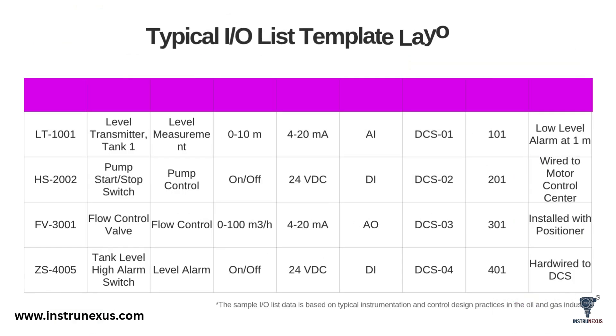Let's look at another practical example. This table shows a typical IO List layout filled with sample data. The first row has Tag No. LT-1001, with service 'level measurement for Tank 1.' The signal type is 4-20 milliamps and its range is 0 to 10 meters. This is a transmitter sending a signal to the DCS, so its IO type is analog input (AI). It's wired to DCS cabinet 01, terminal 101, and the remarks note a low level alarm at 1 meter. The second row, HS-2002, is a pump start/stop switch – its signal isn't a range, it's just on-off, making it a digital input (DI). This level of detail, repeated for thousands of points, is what it takes to build a plant.